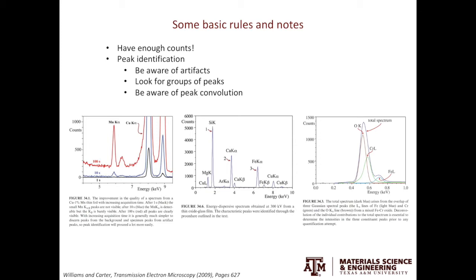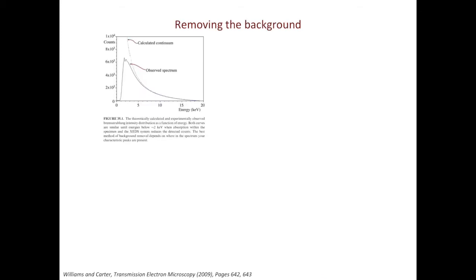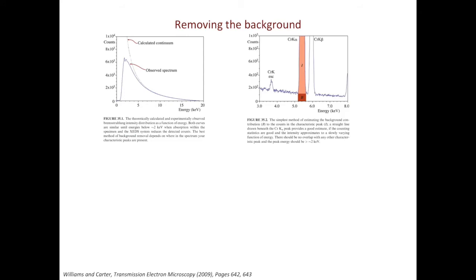For the elemental quantification from EDS, we can apply the same philosophy. A layman may just hit the quantify button and write down some numbers, but you should understand what happened behind the scenes. To perform quantification, the first thing to do is to remove the background. Remember in EDS, you have the characteristic X-ray peaks on top of the continuum Bremsstrahlung X-ray background.